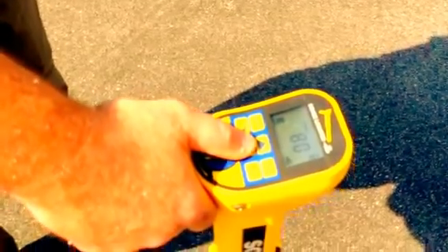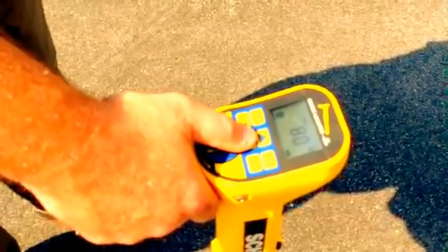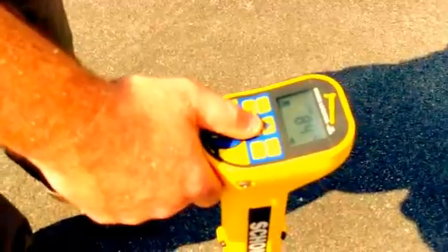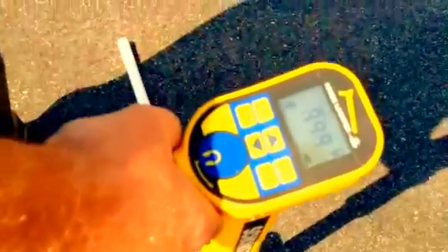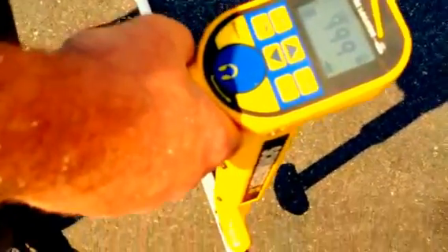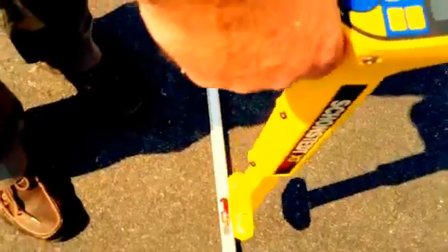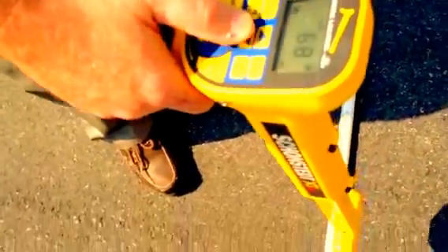Now, this will help me pinpoint the sonde's position within the pipe more accurately by keeping my sensitivity low. Notice that the peak is going up again when I am directly over and in line with the beacon. I'm getting even more precision by lowering the sensitivity even further.